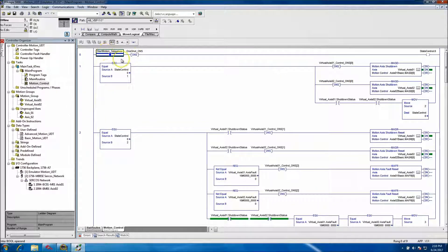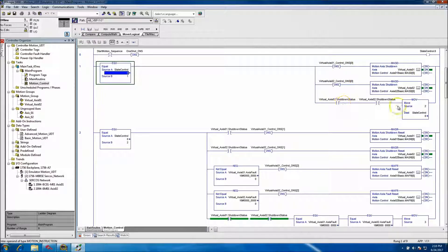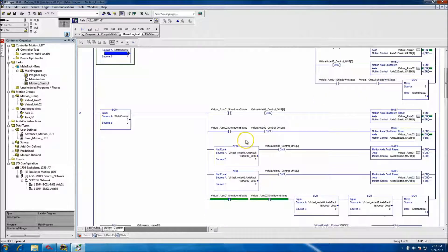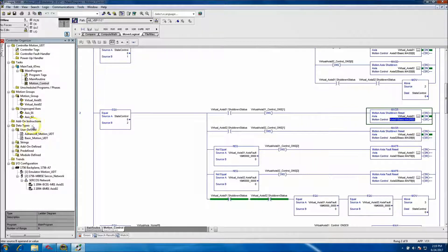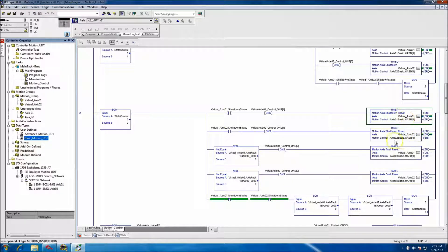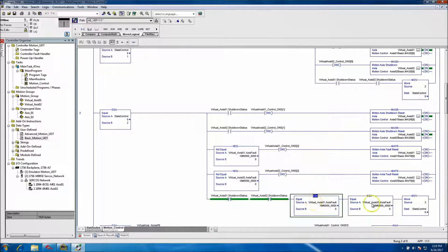The state logic is not online right now, so I'll explain it. You start the sequence, which loads a 1 into state 1. It shuts down both axes. When they're shut down, they go to state 2, which does a shutdown reset. If they're faulted out, you reset the fault. We are using the UDTs we created in every one of these instructions.